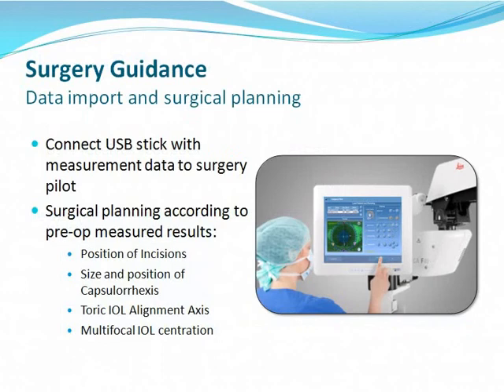Here the surgery pilot — you connect the USB stick and then you can plan your position of the incision, the size and position of the rhexis axis, and if you use a toric lens, the alignment axis.